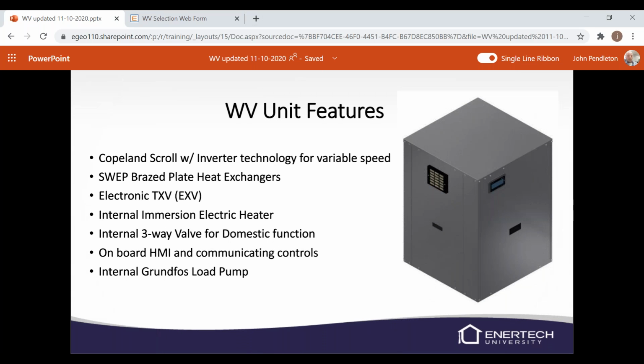Some of the features, again, it is a variable speed compressor. It's a Copeland scroll with inverter technology. There's two brazed plate heat exchangers in there, one for the load, one for the source. We're using an electronic expansion valve or an EEV or EXV, whichever you like to call it. We have to use the electronic expansion valve because of the variable speed, and a thermal expansion valve won't respond quick enough for us. So we're going with the EXV. One thing that is nice about the EXV, we probably won't have an issue with it being restricted.